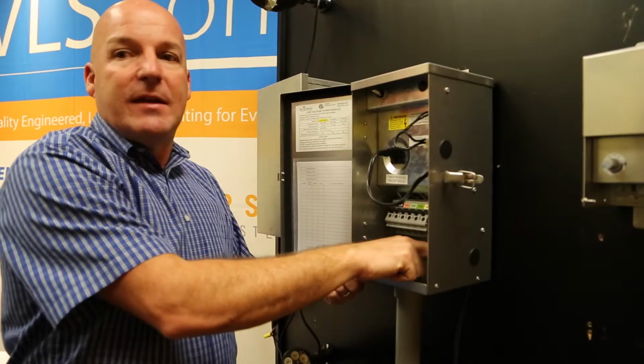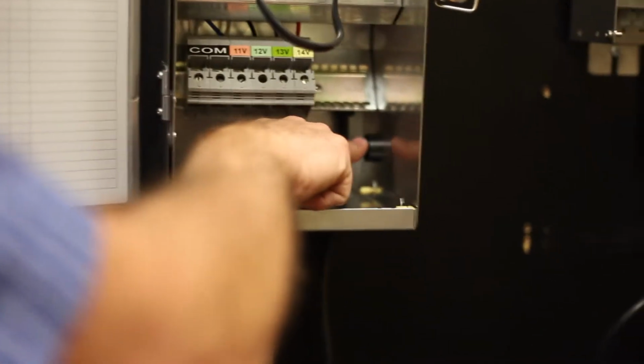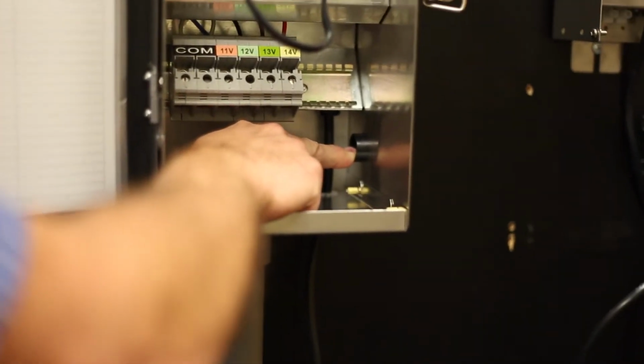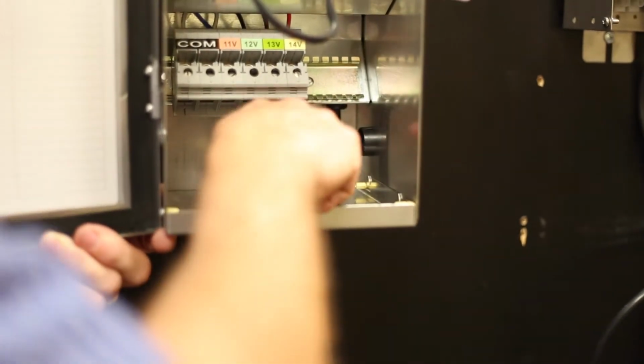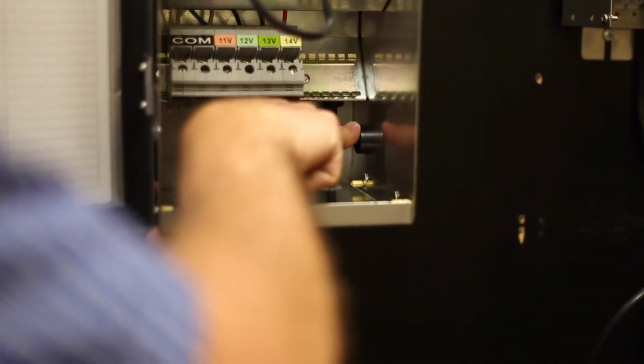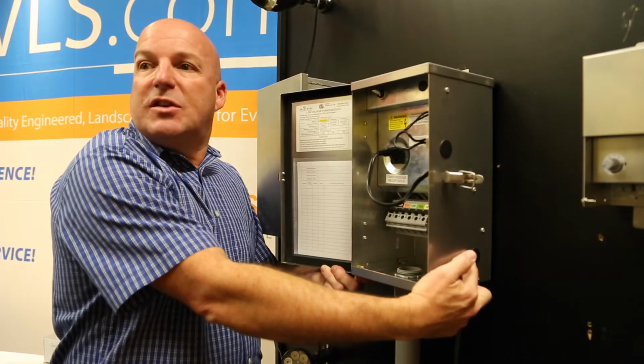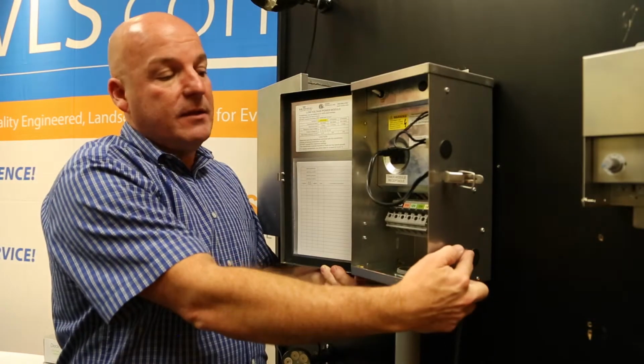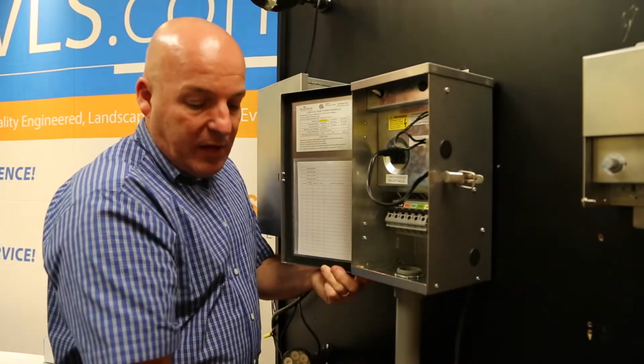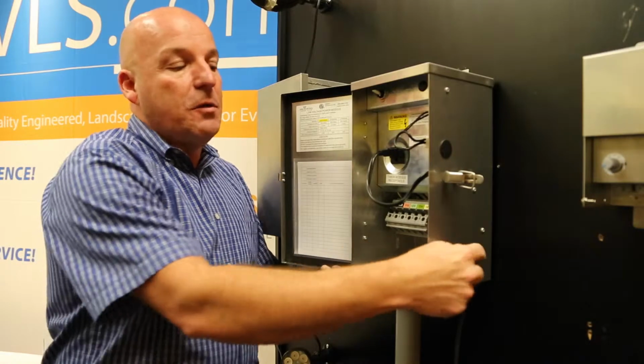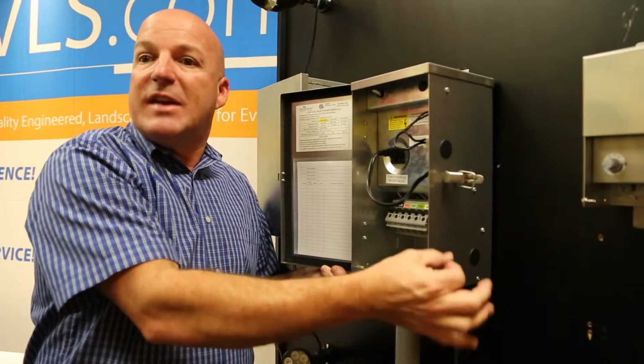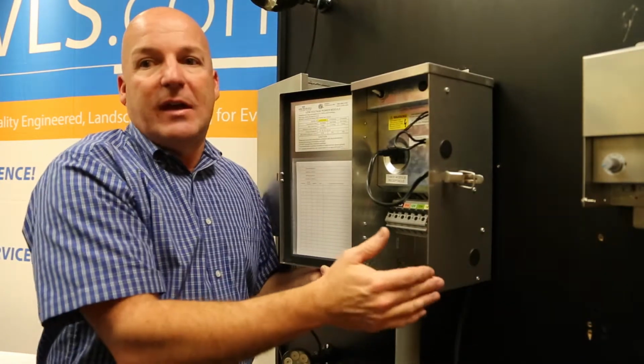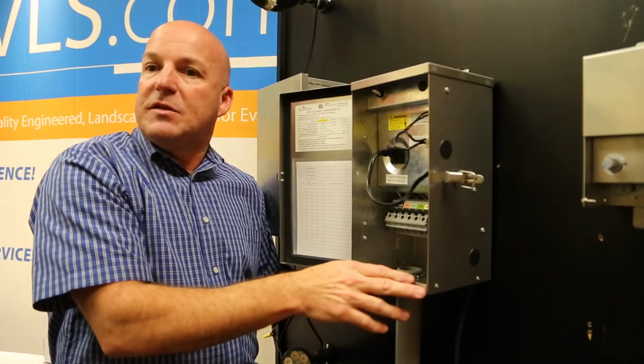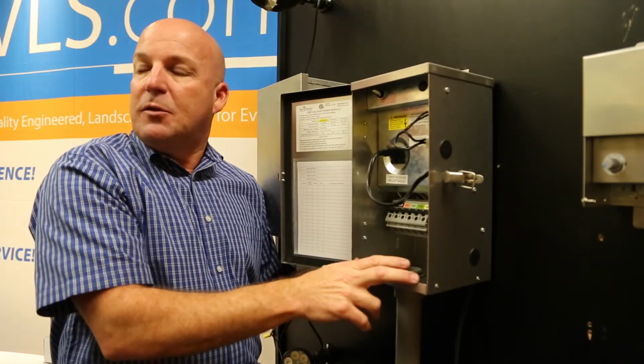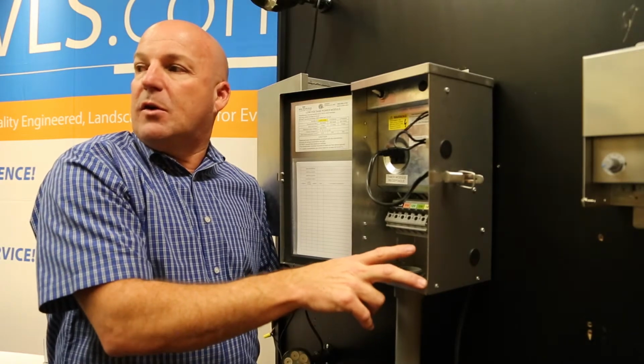On the bottom, we added the ability to hardwire the transformer. For the hardwiring knockout, you take the bottom plate out, take the power cord, knock this out, and run the power cord through the hole and through an electrical junction box, generally called a conduit. You'd cut the plug off the end and do that wiring inside the conduit or junction box. By doing that, you do not void the warranty on this transformer — it's still UL 1838 approved and meets NEC code.